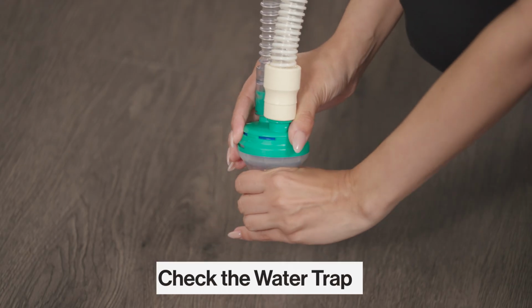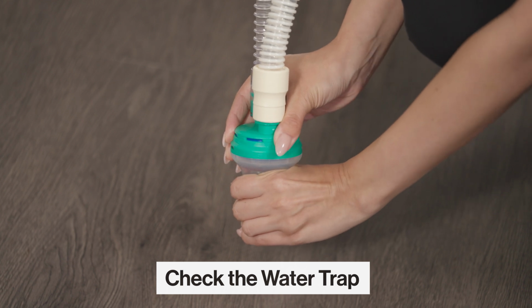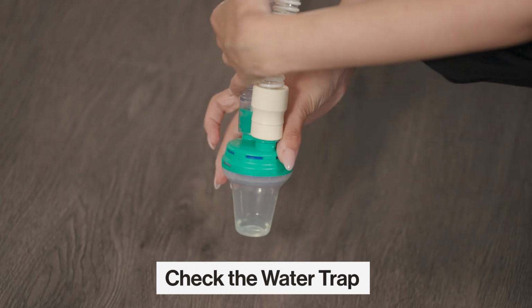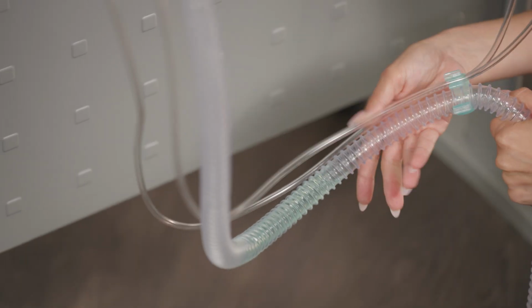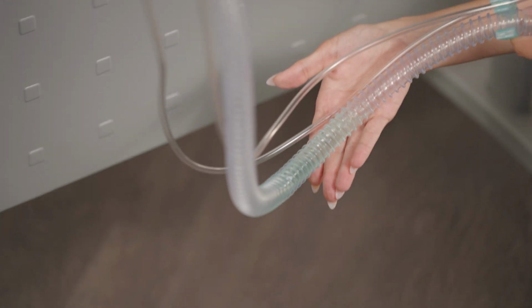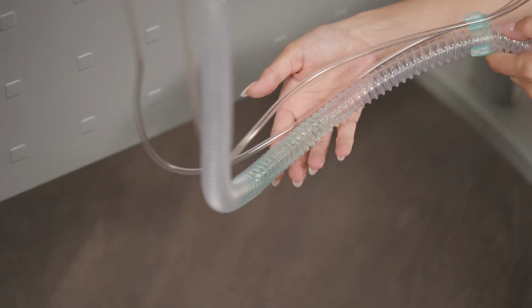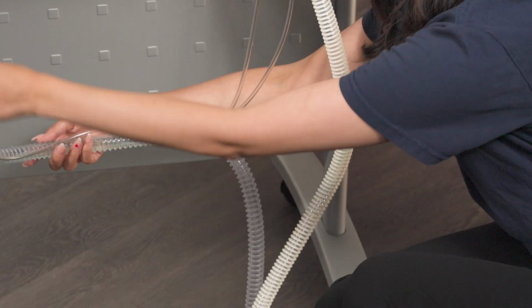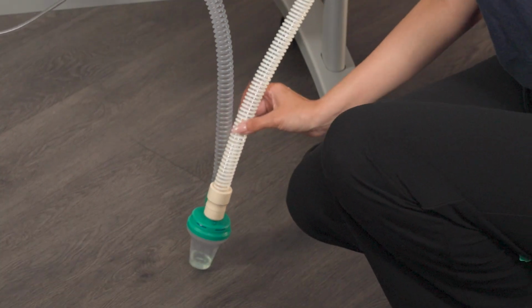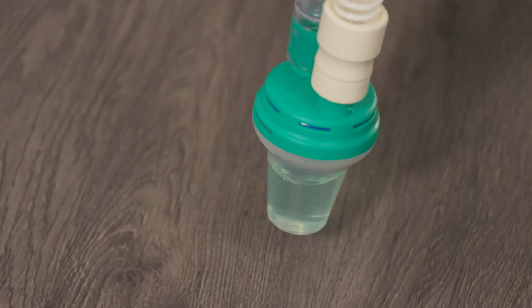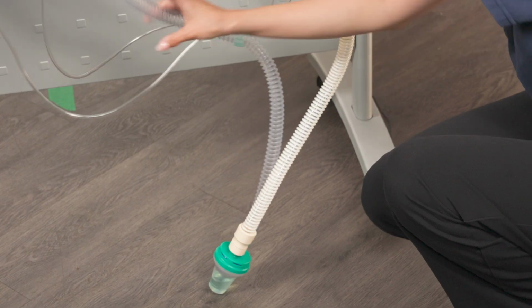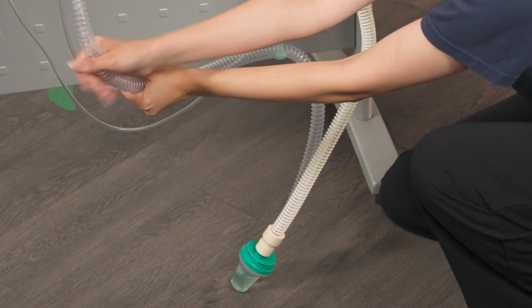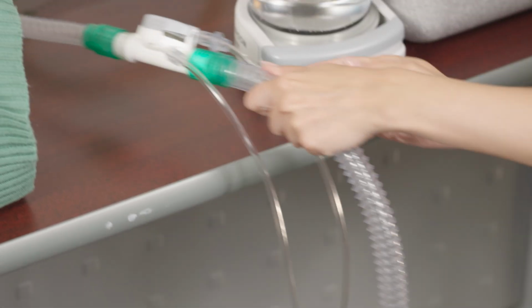Next, I'm going to examine the water trap and make sure the cap and cup are connected tightly together. Here, I find water condensation accumulated in the circuit. This can cause a high pressure occlusion alarm. I'll dump all water back towards my water trap. Let's finish by walking our hands all the way back to the exhalation valve and up to the flex tube.